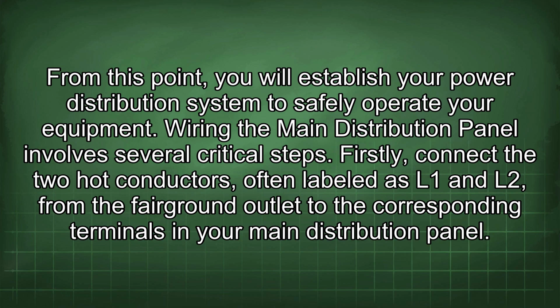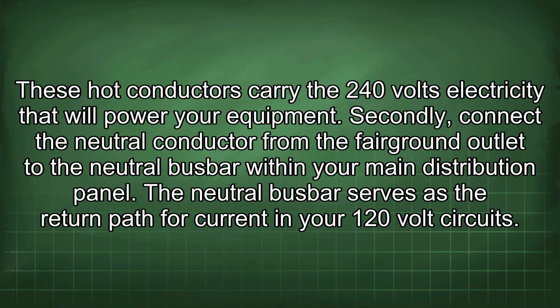From this point, you will establish your power distribution system to safely operate your equipment. Wiring the main distribution panel involves several critical steps. Firstly, connect the 2 hot conductors, often labeled as L1 and L2, from the Fairground outlet to the corresponding terminals in your main distribution panel. These hot conductors carry the 240 volts electricity that will power your equipment.